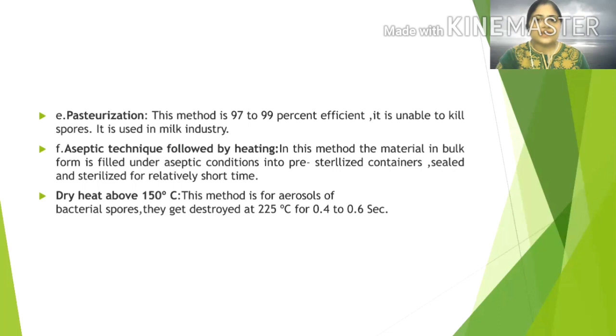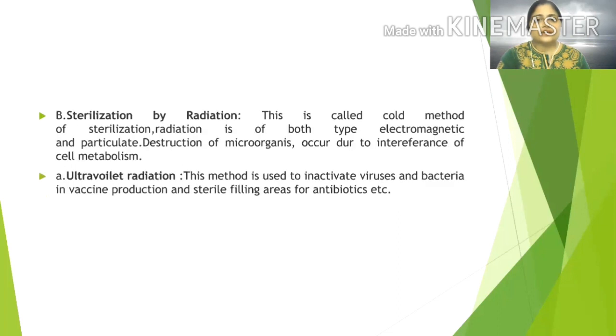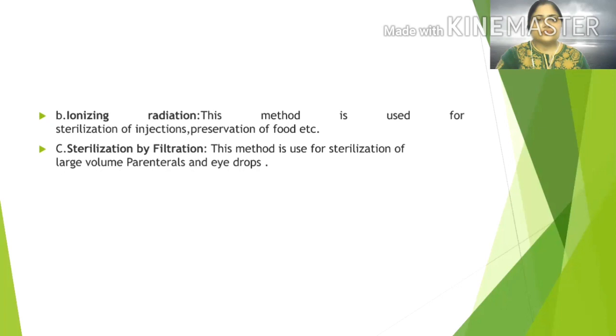In this method, the material in bulk form is filled under aseptic condition into a pre-sterilized container, sealed and sterilized for a relatively short time. So here, the container is not contaminating the sterilized pharmaceutical, because the container is already sterilized. This is an efficient method for pharmaceutical and food preparation. Next method is dry heat above 150 degrees centigrade. This method is for aerosol of bacterial spores. They can be destroyed at 225 degrees centigrade for exposure of a very short time, 0.4 to 0.6 seconds.